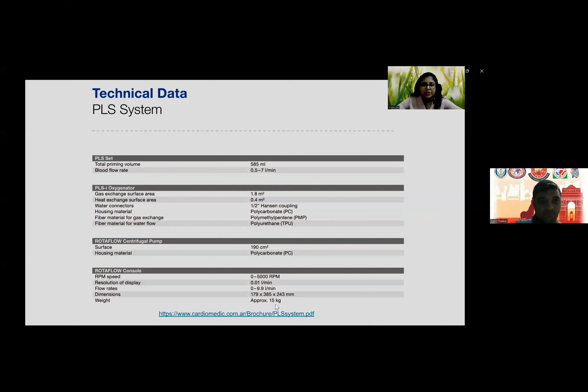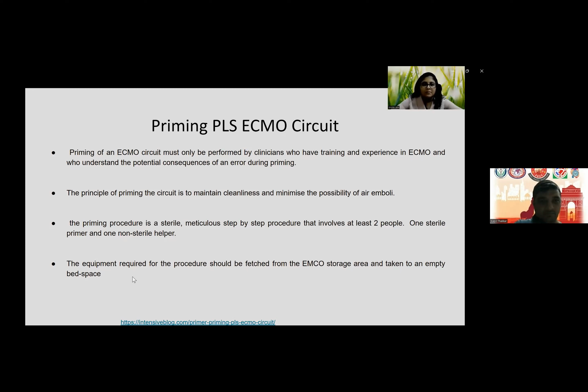So priming the PLS ECMO circuit. Priming must only be performed by clinicians who are trained and experienced in ECMO and who understand the potential consequences of an error during the priming. The principle of priming the circuit is to maintain cleanliness and to minimize the possibility of air emboli. The priming procedure is a sterile, meticulous, step-by-step procedure that involves at least two people, one sterile primer and one non-sterile helper. The equipment required for the procedure should be fetched from the ECMO storage area and taken into an empty bed space. All right.